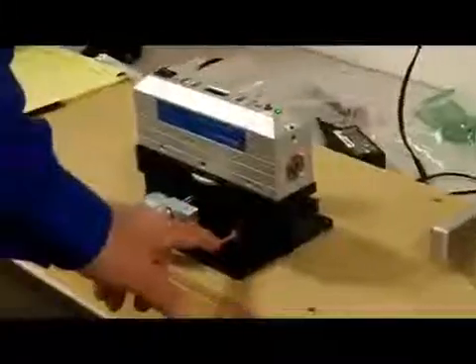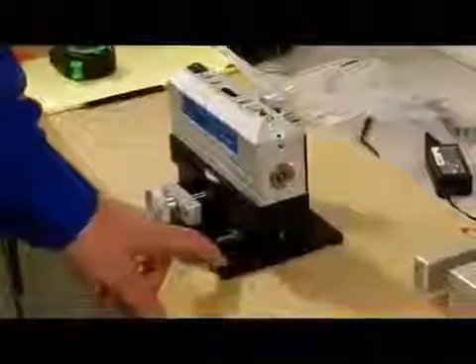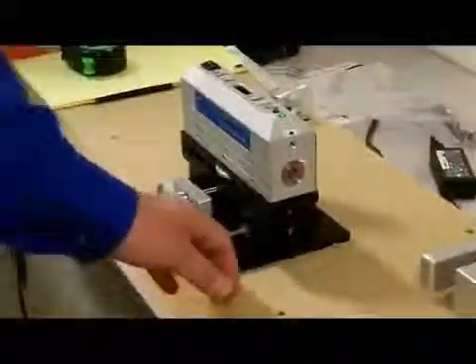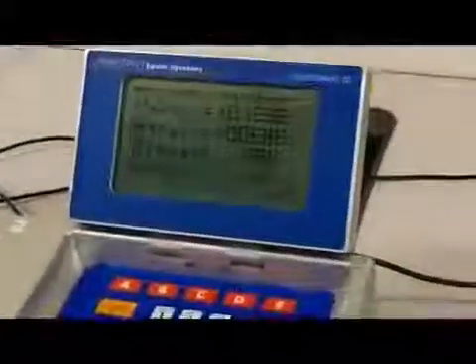Now that I have my target values I can go ahead and adjust my four axis mount using the pitch control and the yaw control to establish my vertical and horizontal position. I'm using my location number two as my calibration point or to establish these target values. So I know that my vertical target was 0.1431, which I will now adjust my pitch control until I achieve that result on my vertical reading. So that's 0.1431.